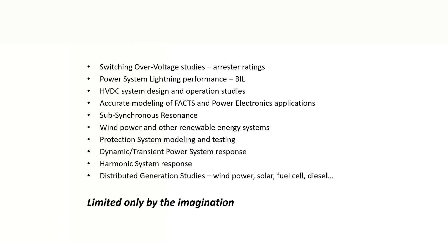More recently, PSCAD has become a very attractive software to simulate renewable integrations like wind and PV, especially in low short circuit areas where there are some issues. It is also used for specific protection scheme development — especially related to heavily renewable-flooded generation areas. As more and more renewables come into the power system, the short circuit level goes down, and sometimes traditional relays which rely heavily on short circuit currents may fail or have issues. Those kinds of special studies are normally performed in PSCAD.